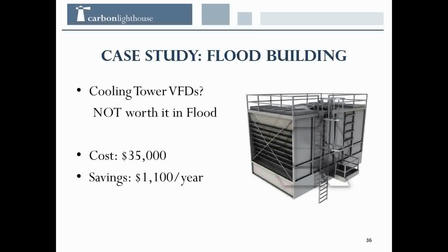Best practices would typically recommend installing variable frequency drives on your cooling tower fans. In this building, that was going to cost somewhere between $30,000 and $40,000 depending on the bids we got and which firm we used. But it was only going to save $1,100 a year.